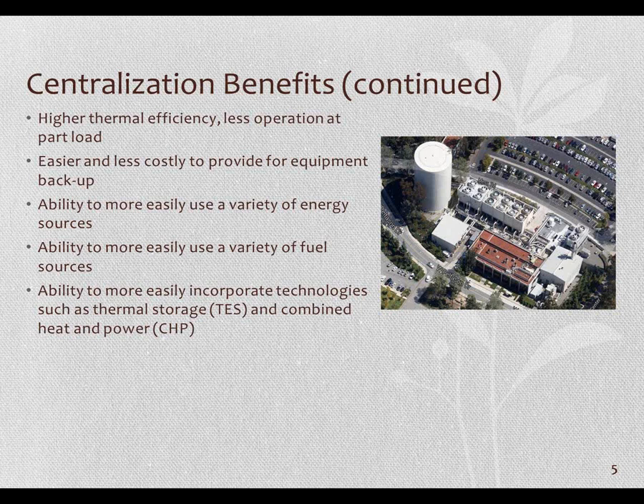Likewise, it's easier to provide backup. Think about having a boiler in every building. If I want a backup, I need to put an additional boiler, so I'm having 2 times the amount of boilers that I would need. Versus a central plant, if I have 4 or 5 boilers, I can easily just add 1 more boiler to provide for my backup capacity.